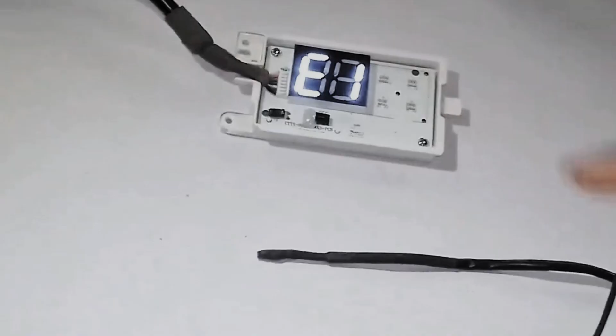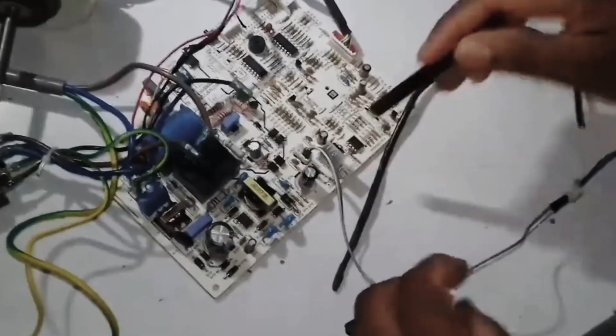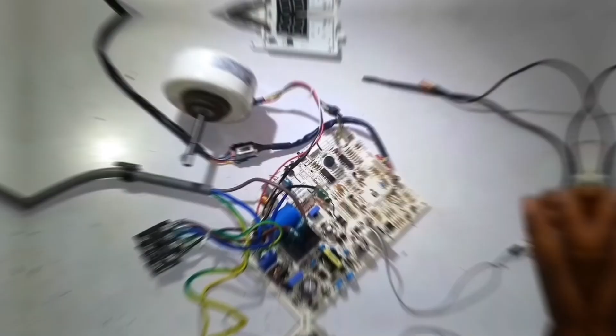When the E1 error appears on your air conditioner's display, it means there is an issue with the room temperature sensor. This sensor is connected through a specific connector, as you can see here. If the sensor becomes faulty, gets short-circuited, or if the error does not disappear even after replacing the sensor, it indicates that there is an issue with the PCB. In that case, you will need to either repair the PCB or replace it. Now, we will talk about the next error code.